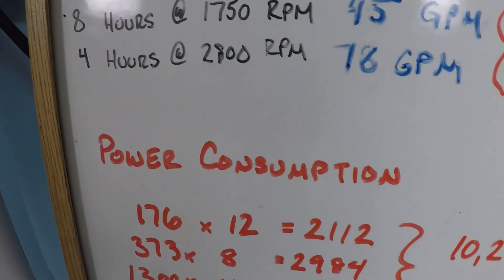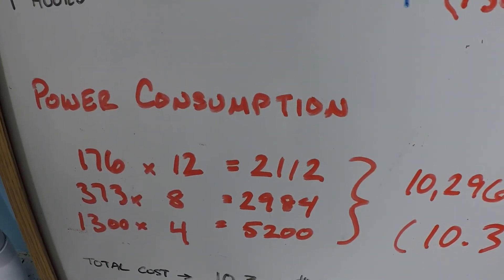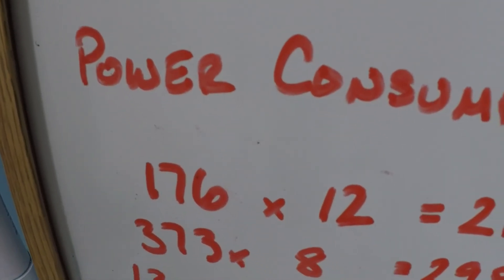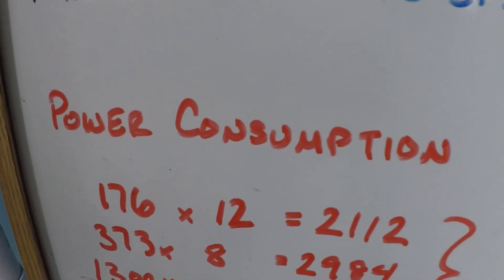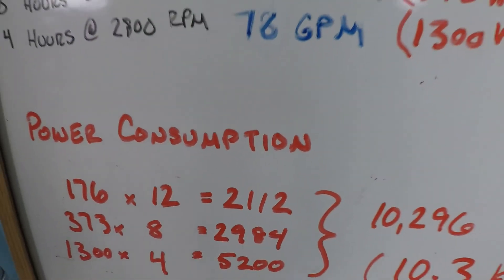And that's why with a variable speed pump the goal is to not turn it off. You want to run it all of the time, 24 hours a day, with a lot of those hours being at low RPM operation where you get quite a bit of filtered water for not all that much power consumption.